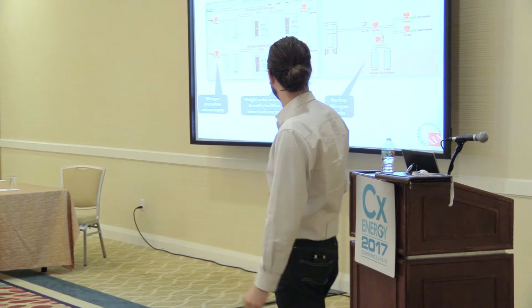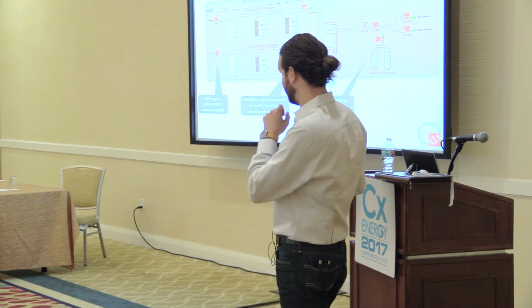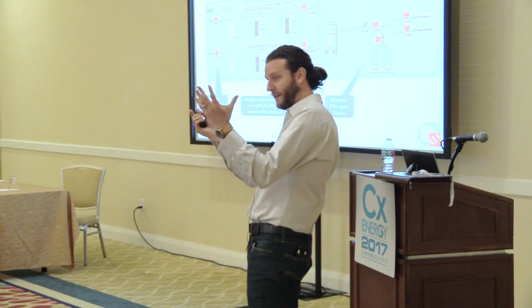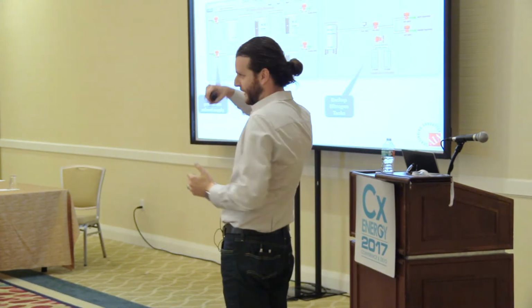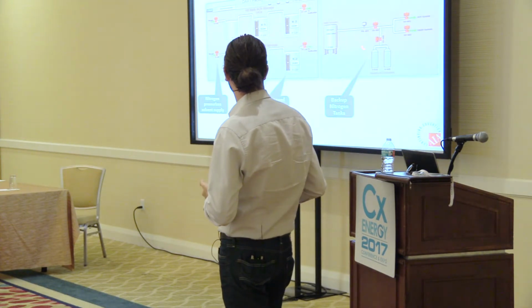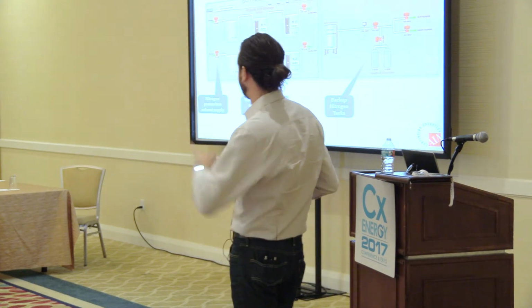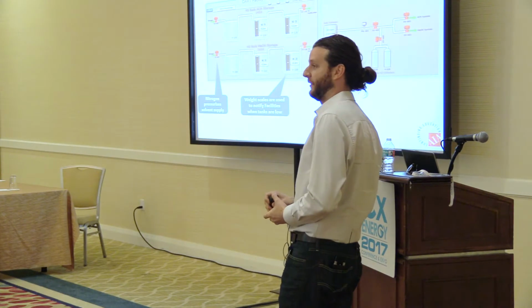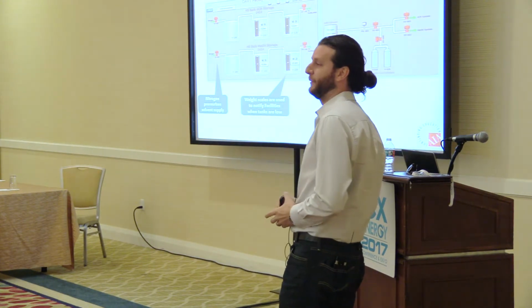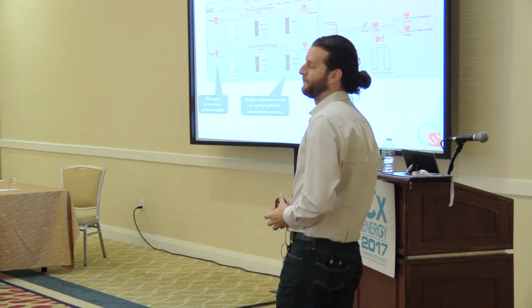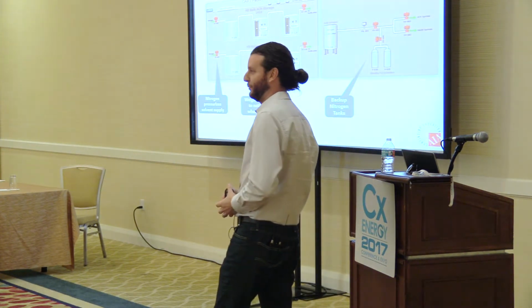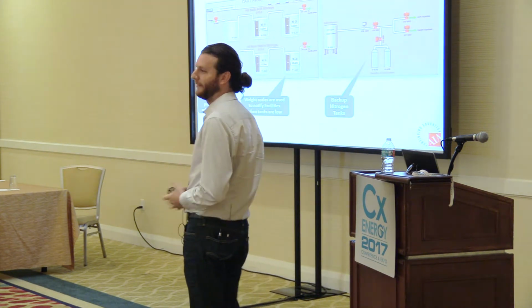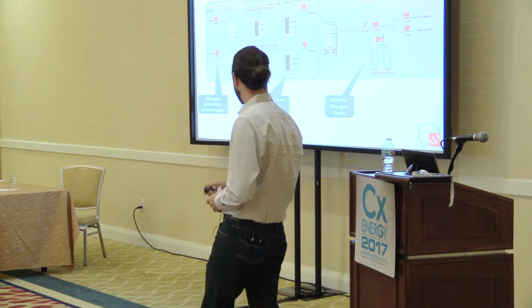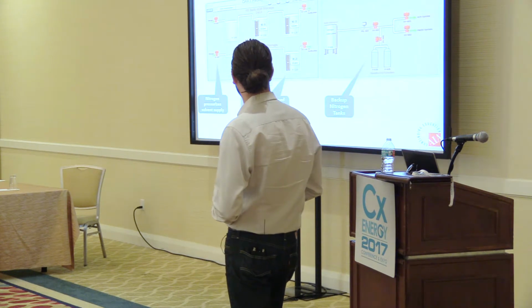Secondly, they had a backup nitrogen system. So if the main system failed, a low pressure sensor would open. During commissioning, we actually went out there and we just shut off the bulk nitrogen system. The low pressure switch opened, these valves switched positions, and they went to a backup nitrogen system that allowed their processes to be continued. Some of these processes are very expensive to run, and if you fail right in the middle of the experiment, it's no good. So we try to reduce that at all costs.